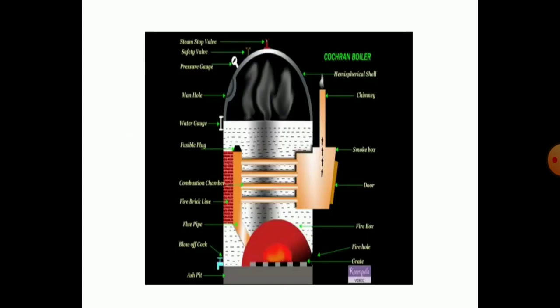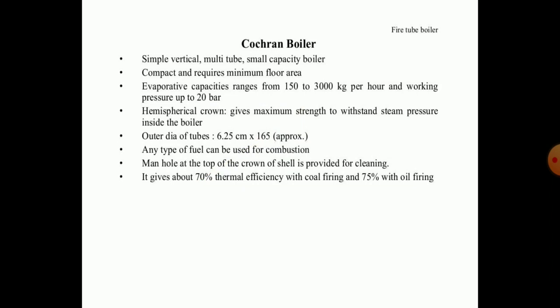Now we see the fire tube boiler. In front of your screen, a pictorial view of a fire tube boiler is shown, including the parts, tubes, chimney location, and cross-sectional area. At the top, the crown-shaped area contains the high pressure, high temperature steam. The Cochran boiler is simply a vertical, multi-tube, small capacity boiler which is compact and requires minimum floor area. It has an evaporative capacity ranging from 150 to 3000 kg per hour, while working pressure is up to 20 bar. The hemispherical crown gives maximum strength to withstand the steam pressure inside the boiler.